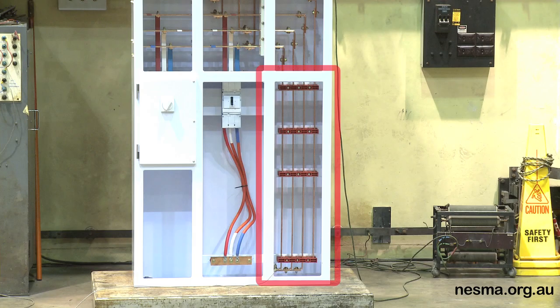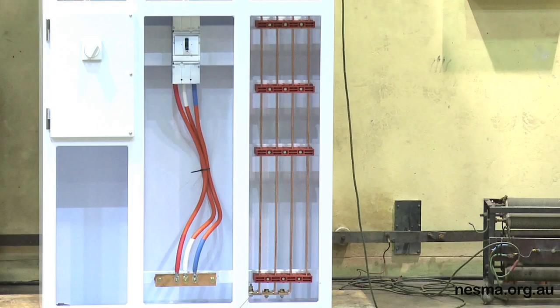So test 1 is going to be a bolted short circuit on main bus bars in the far right hand section of the switchboard. Note all other parts of the switchboard are isolated from this test. Bus bars are spaced at the correct centres. We've used bus bar supports which are commonly used in the industry. Supports at the top have a maximum spacing of 300mm, and the supports at the bottom have a maximum spacing of 500mm. A test current of 50 kA will be applied to the switchboard for 1 second.